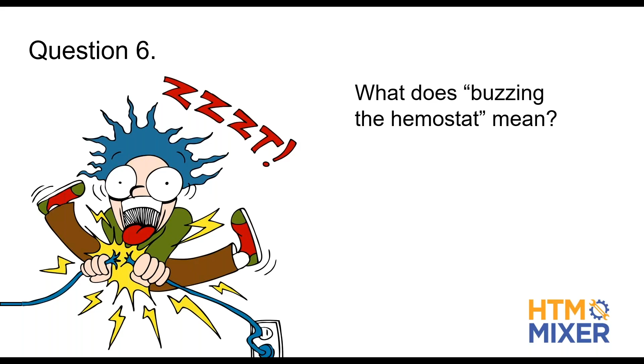In class, we talk about how generators work: wherever that electrode is, it completes a loop back to the generator. So we're taking into consideration what tissue resistance we're running into. You can see the human body has a lot of different resistances, from muscle, eye, skin, kidney, pancreas, liver, gallbladder, all the way up. So when that comes through and runs into a higher resistance, the generator changes voltage and current because that controls power. It's constantly doing that. I'm only telling you that because right now I want to talk about buzzing the hemostats, because it's way down there, it's low. Buzzing the hemostats is when they don't care to use the forceps. They are a bipolar device. Instead, they take the forceps and they put it across the vessel.